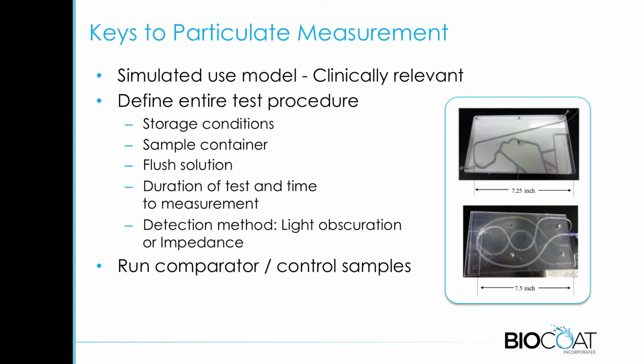The other piece is that you need to define the entire test procedure, because there are a lot of ways that you can change the values. For example, defining the storage conditions for your device and the solutions. The sample container: is that plastic, is it glass, how are you washing it? Flush solutions: how well are you filtering those, is that water, is that PBS? As well as things like the duration of time between testing and the time that you're actually measuring the particles. And then the detection method. USP talks about either light obscuration or impedance methods, and either one can work, but you need to define which it is.